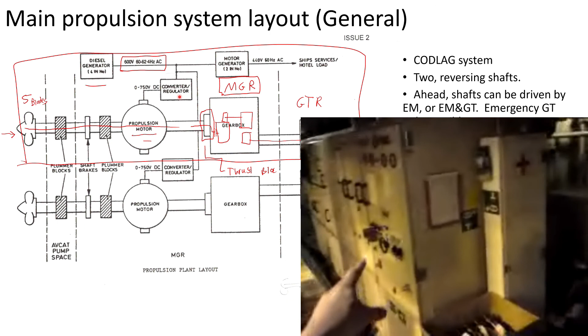Likewise, the thyristor converter regulators are 4-quadrant converters, and they are much larger than the equivalent on, say, an electric locomotive. And one of the reasons that they're much larger, even though they're not particularly powerful, is because of the amount of harmonic filters that they had to have. Because the last thing you want is to inject harmonics into your propulsion motor and then your shaft, where every submarine for 1,000 miles is going to hear you.